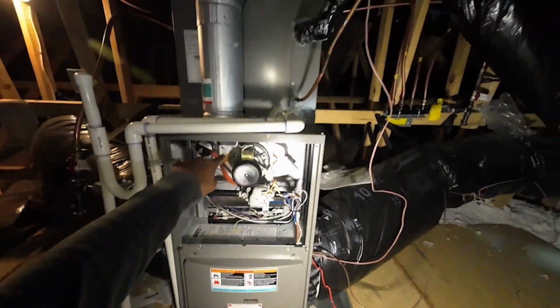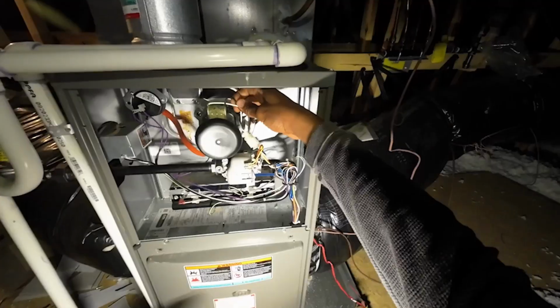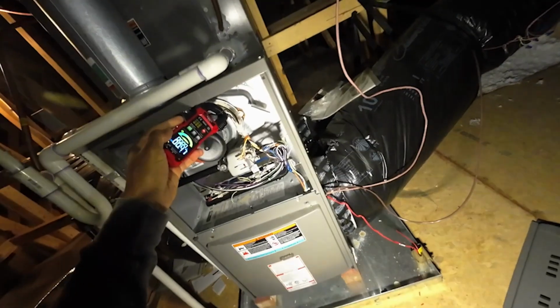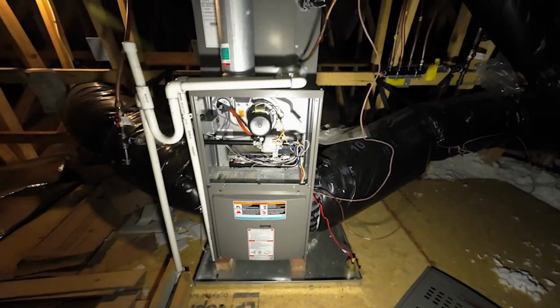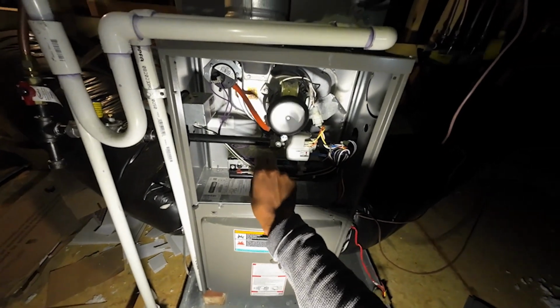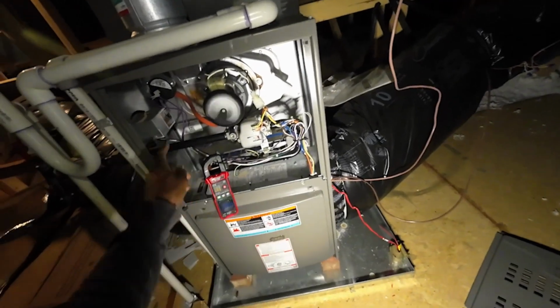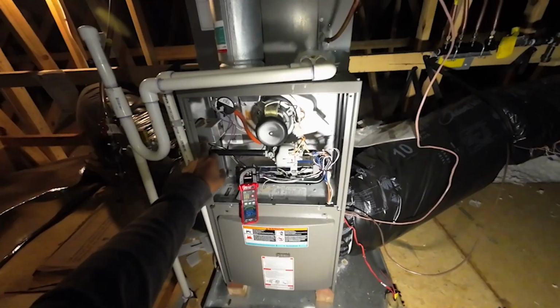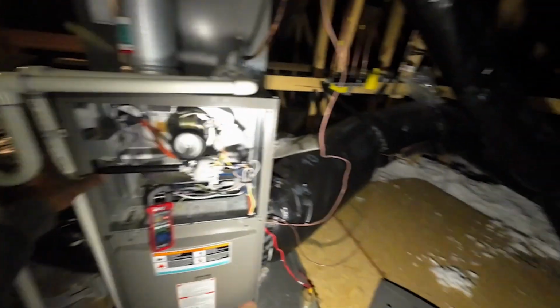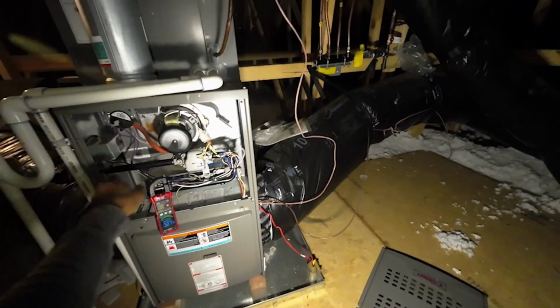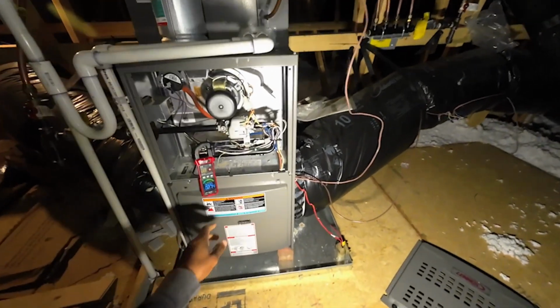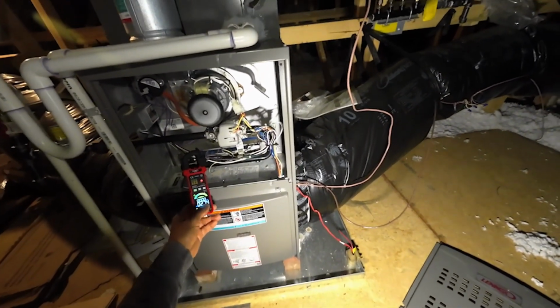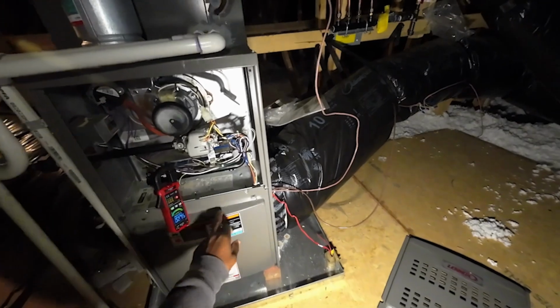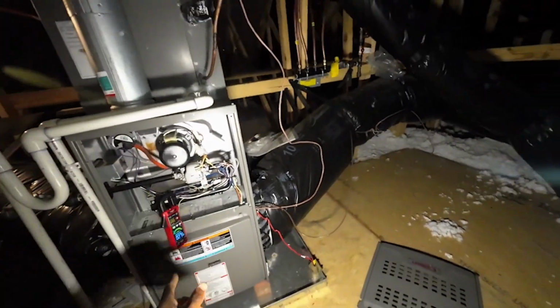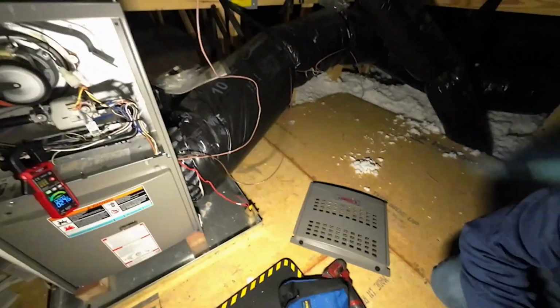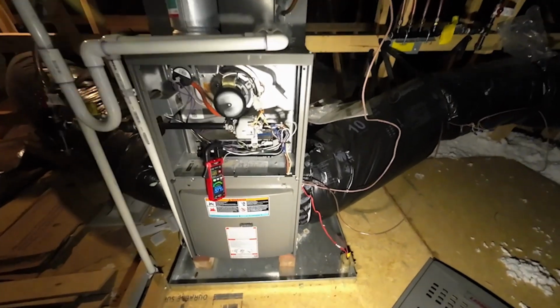This is the outlet of the inducer out of the house. Okay, check my amp draw here. So we got a 0.48 on my inducer amps, and then this is a total amp draw. So that means this is basically the line voltage coming in, high voltage, 120 volts, and it's powering the whole furnace. So it's a cumulative voltage. So you see 2.74, that means it's capturing the blower amps and the inducer amps. So if I just want the blower amps, I'm going to subtract what I captured for the inducer amps. That makes sense?